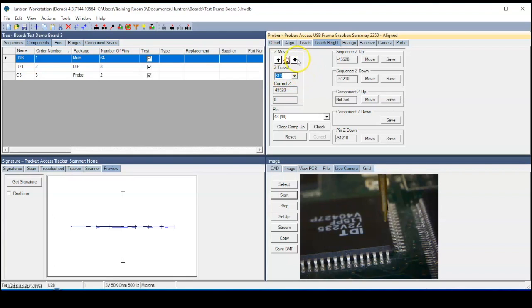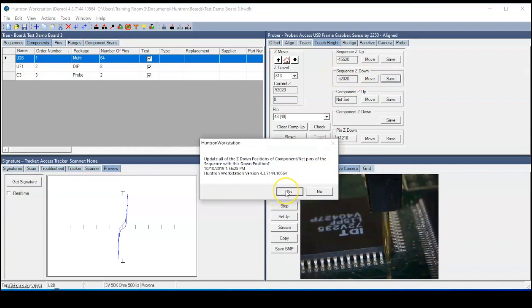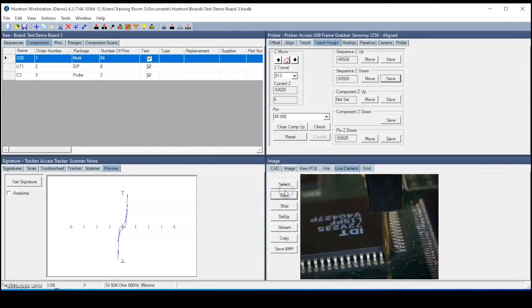So I'm going to change to a smaller increment here and then gently lower the probe tip down. Notice how it's coming right down on pin number 43. Provided your offset was done correctly, this probe should go exactly where you teach it. Notice that just as it made contact, we got a signature over here in the signature pane. So that's good, but I want to give it just a little bit more compression downward, so we'll click down one more time just to put a little bit of force on the probe tip. And then save this as the sequence Z down. That means this will be the down position for all the components in the sequence.